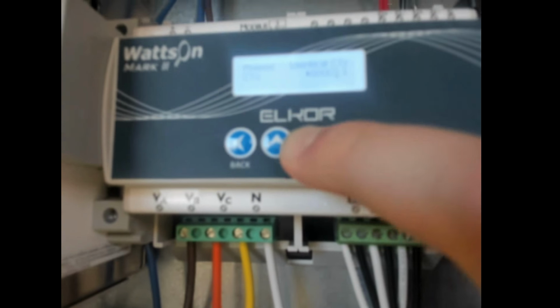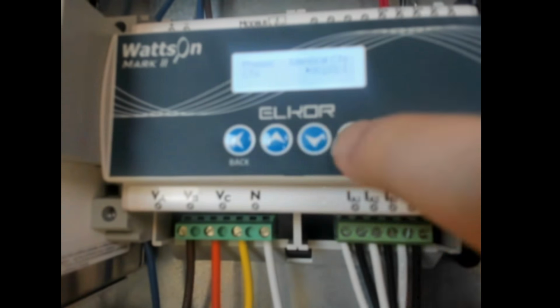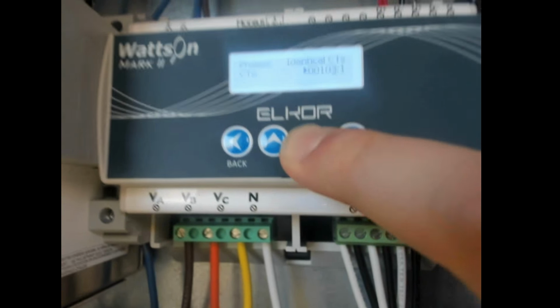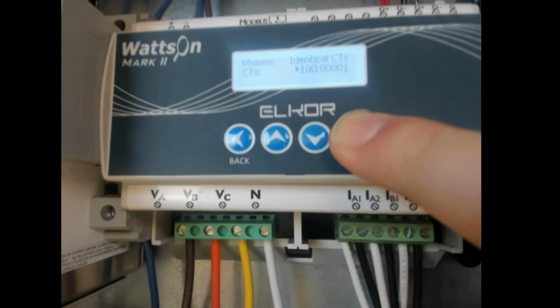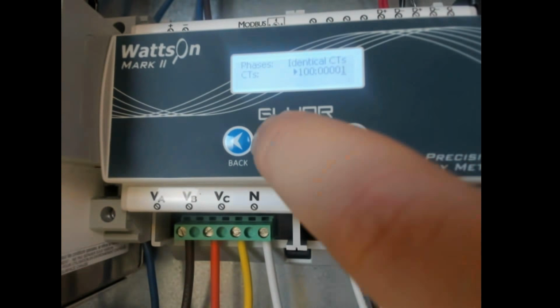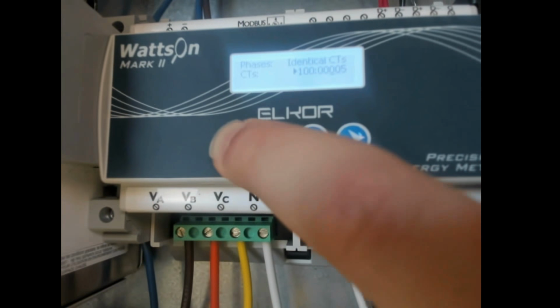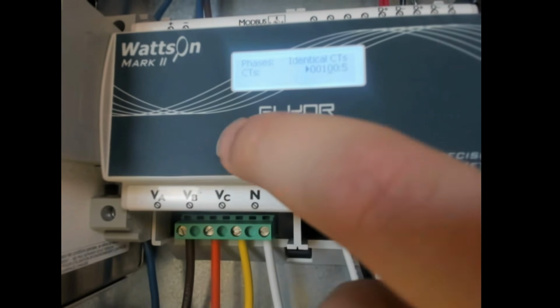So rather than setting it to X number to 1, it's going to set the same ratio, X number to 5, to 1. So if I have a 500 to 5 amp CT, that would mean it's 100 to 1 CT. So I would go over here and change this to 100 and cycle through to change this to 0. Oh, hang on. That way. Okay. Oh, actually, you do have the option to do either. So you could do 100 to 1, or you could do 500 to 5. It's the same thing as far as the meter is concerned. It's just whatever your preference is.